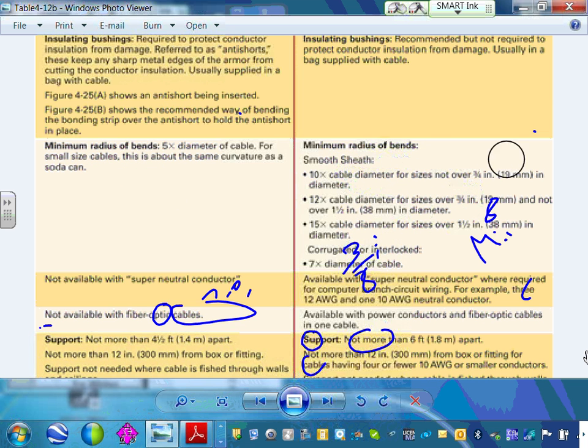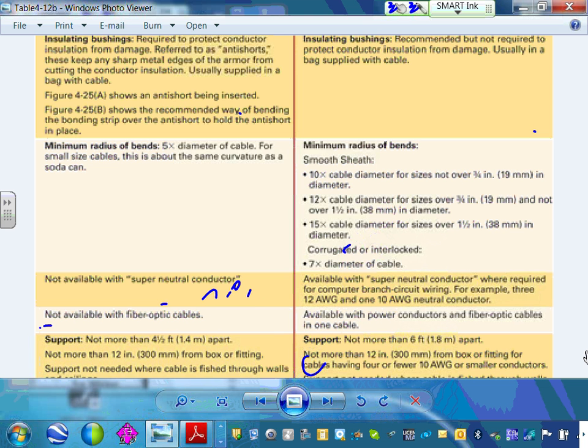Let me go all the way up to here. Because this is 5, which is typical for all cables, but MC cable comes in different sizes. So they give you different multipliers. Here's 10 for a certain range, 12 for other ranges, and 15, as well as 7 times the diameter of the cable if it's corrugated or interlocked. So anyway, there are 2 different types for these, with different multipliers for them.